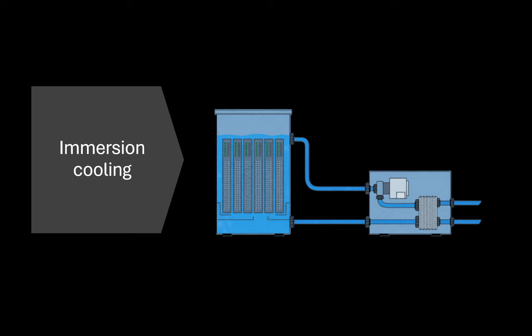In immersion cooling, servers are submerged in dielectric fluid to quickly dissipate heat. The coolant is then circulated in a heat exchanger to be reused. On the lower end, you'd still only need a mass flow rate of 2.63 kilograms per second to keep up with current AI demands. However, both methods are mechanically complex and have high maintenance costs. This means it's difficult to retrofit old data centers with the new cooling methods, and it's far more efficient to install in brand new data centers.